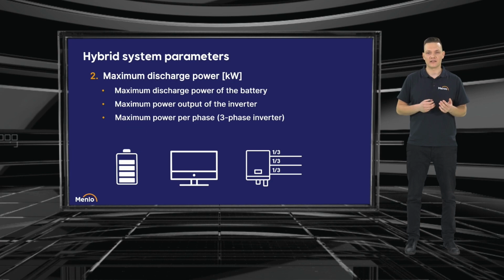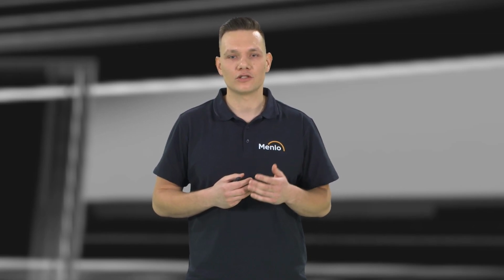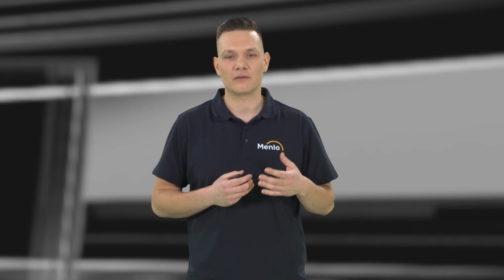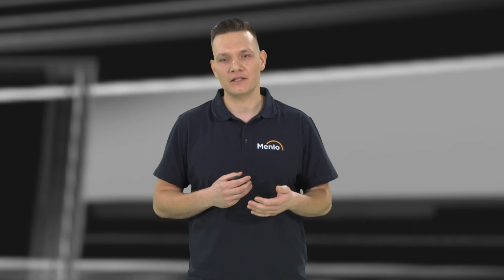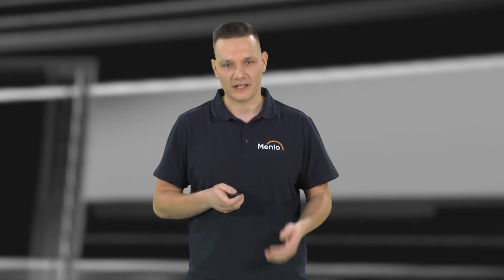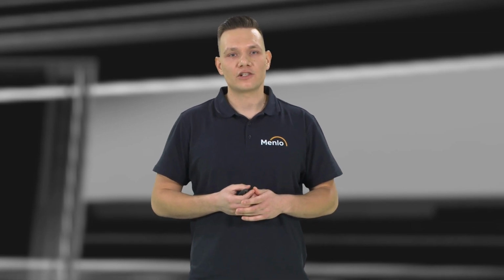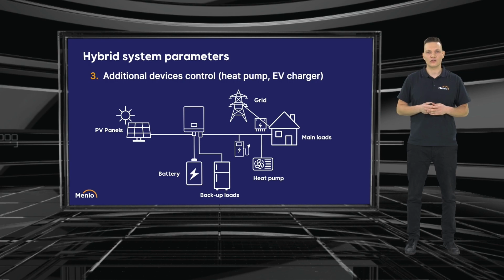Then we have maximum power per phase in a three-phase hybrid. Most inverters cannot put the whole nominal power of the inverter on only one phase. So you need to check what percentage of the nominal power of the inverter you can put on one phase, and depending on that, connect devices to that phase. Then we have additional devices control. A lot of hybrid inverters not only control the battery, but you can also add other devices, such as an EV charger, a heat pump, or smart home appliances. That is also something you should know and study before you buy an inverter.